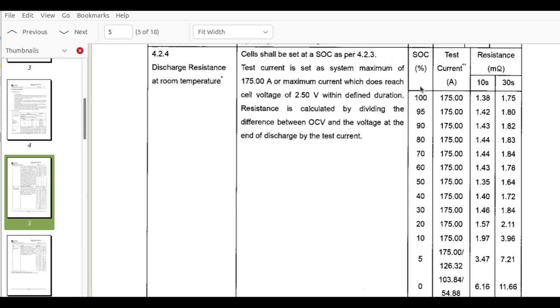If you look at this table, it says start at a state of charge of 100%, test current at 175 amps for either 10 seconds or 30 seconds. I'm going to do a 30-second test, so you do this calculation: the start voltage minus the minimum voltage the cell reached during the 30 seconds at 175 amps, and that difference divided by the test current gives you the resistance. We'll see what we can do with our battery.